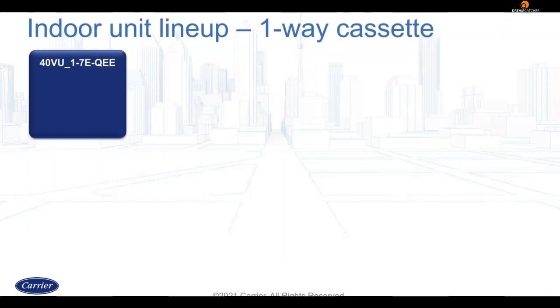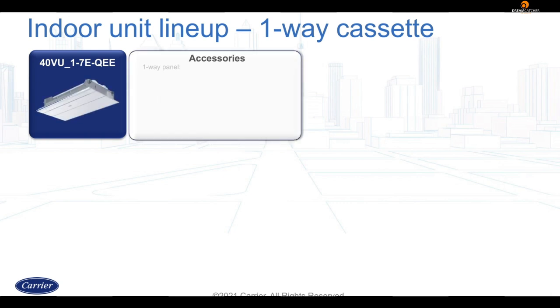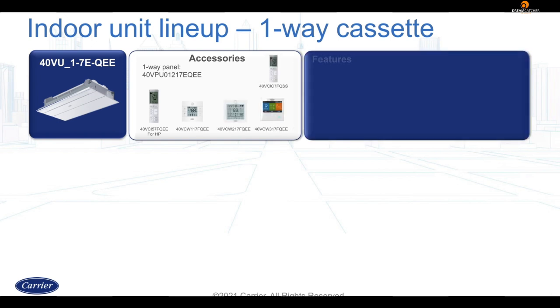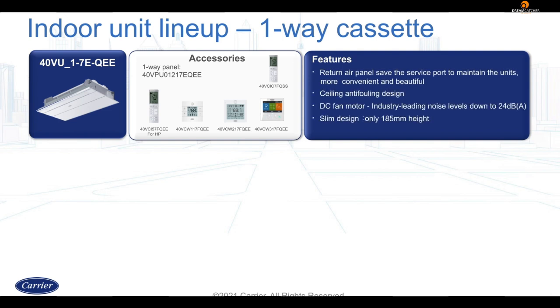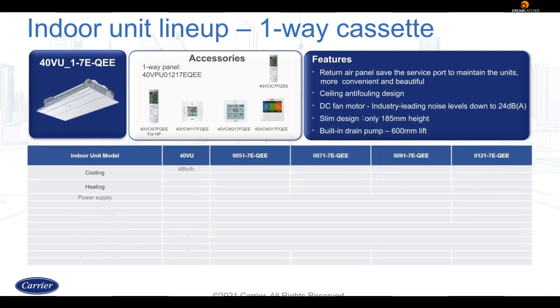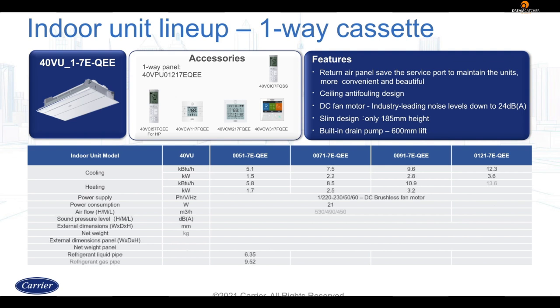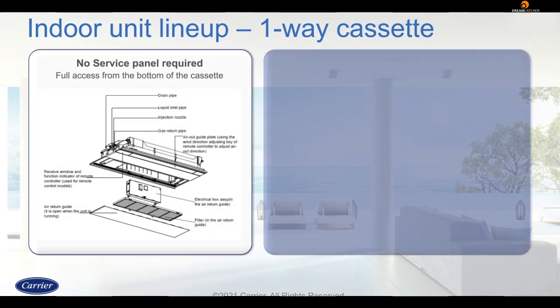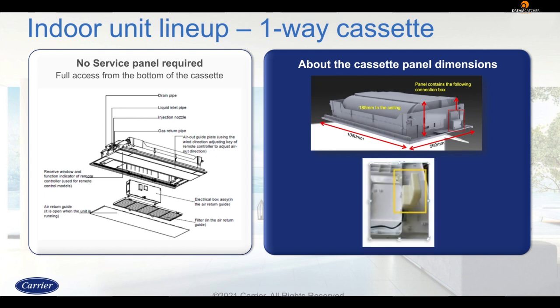The 1-way cassette is suitable for corner air distribution. It comes with a return air panel to maintain the unit, making it convenient and beautiful. It also features a ceiling anti-fouling design, along with an industry-leading noise level down to 24 decibels with the help of the DC fan motor. The slim design of just 185 mm height makes it look elegant, and it also comes with a built-in drain pump of 600 mm lift. The biggest benefit of the 1-way cassette is that it offers full access from the bottom of the cassette, which is why no service panel is required.